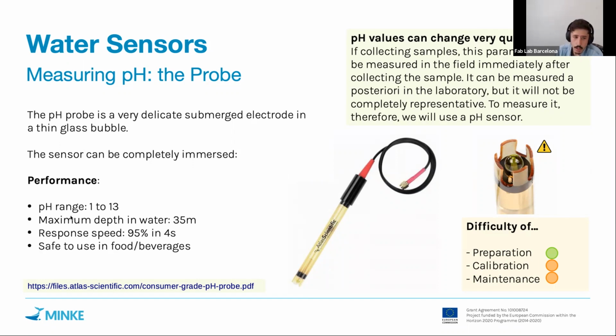In terms of performance, the range it's able to measure goes from 1 to 13, so it's not covering the full pH range. In this case, it can be submerged up to 35 meters, and because of this glass bubble that we have to protect, it takes around 4 seconds to respond, and it's safe to use in general.